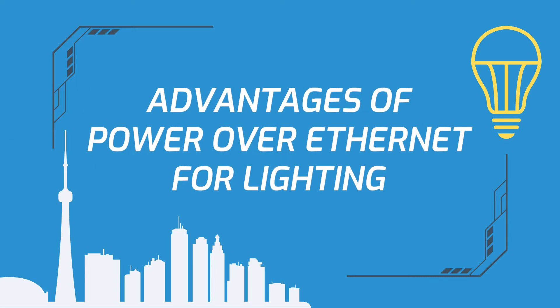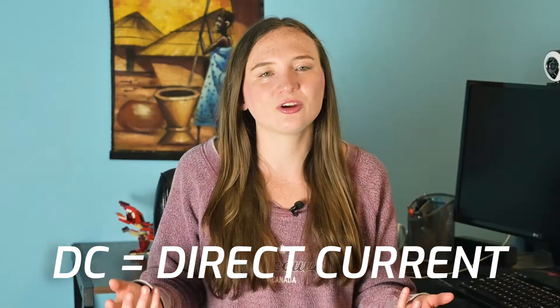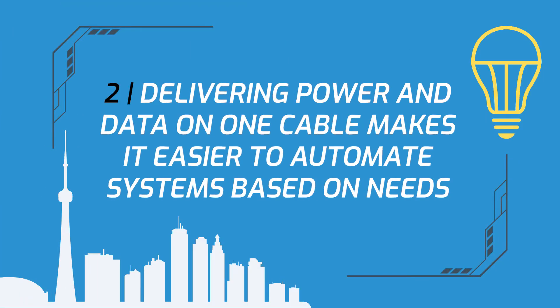When comparing the pros and cons of PoE, we're going to consider this from a lighting perspective to simplify things. These are the main advantages of powering lights with PoE. First of all, PoE distributes low voltage DC power directly to lights. If you're using LEDs, they need DC power anyway, so this cuts back on inefficient AC to DC conversions. Secondly, delivering power and data on a single cable makes it easier to automate and optimize lighting systems for efficiency and real-time occupant needs.